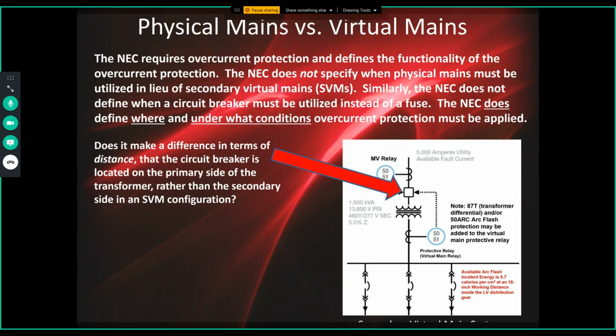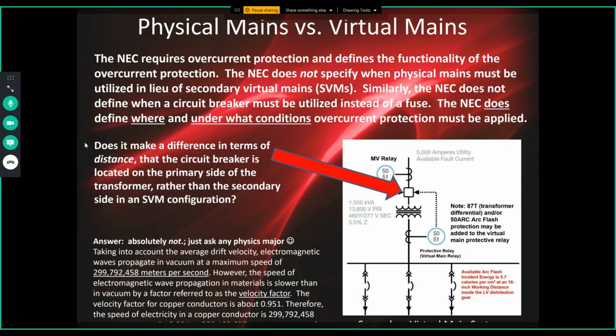So one of the questions I get as well is, does it make any difference, the distance, the fact that we have CTs here, which must communicate to a protective relay, and that protective relay to the primary breaker, rather than have a physical secondary main? Does distance make a difference? And the answer to that is, thanks to the physics of electricity, no. Since electricity travels in theory just shy of the speed of light, effectively at the speed of light, and the speed of electricity in a copper conductor is approximately just shy of 300 million meters per second, no, it doesn't make any difference whatsoever.